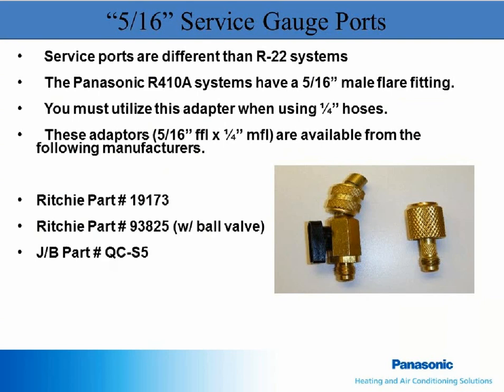All Panasonic cooling only and heat pump products have 5/16 service port connections. Your 410A service gauges require 5/16 hose connections, or you can use a readily available adapter like the one shown from Ritchie and JB. The Ritchie part number is 19173, or the Ritchie adapter with a ball valve is 93825. The JB adapter is part number QC-S5.